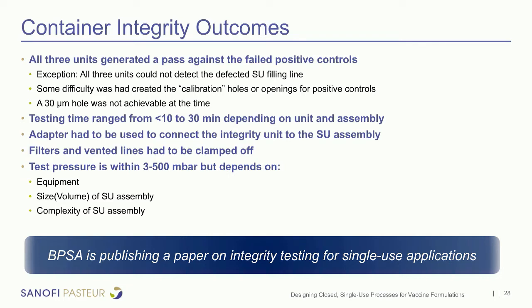I should mention that we had some difficulty creating the calibration holes and openings for the positive controls, which can be mitigated in future using some companies that actually sell these types of calibration holes. For us, we could not achieve a 30-micron hole at the time. But the testing time ranged from less than 10 minutes to 30 minutes, depending on the unit and the assembly. Also, we had to connect an adapter between the testing unit and the single-use assembly. In some cases, it was with a sterile filter, a vent filter, and in other cases, it was a single-use pre-sterile connection that was connected with sterile connectors.